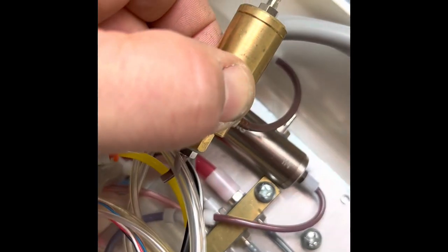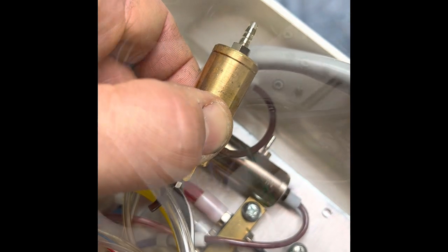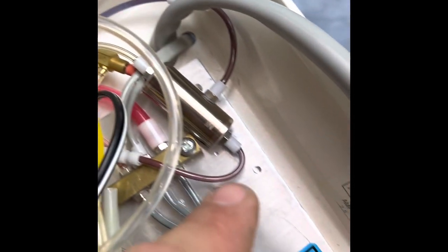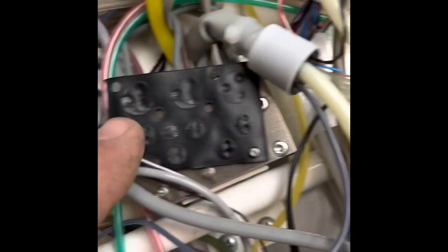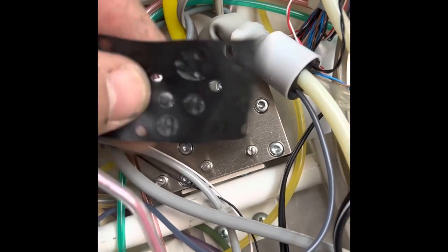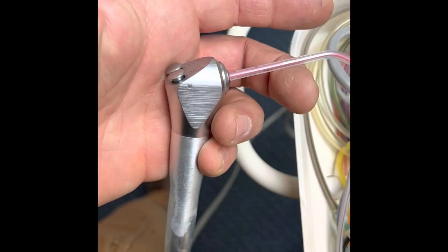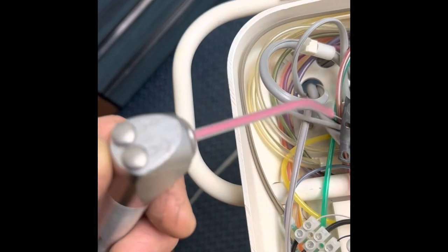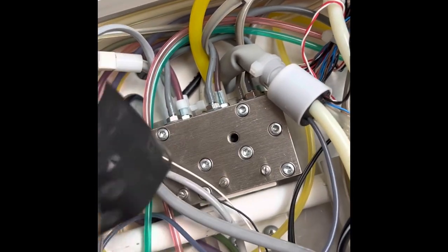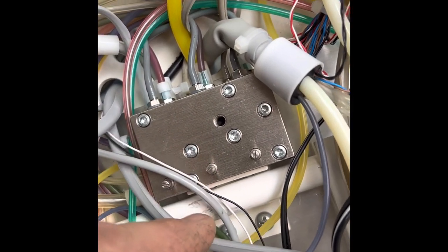Okay, it actually ended up being this diaphragm. The diaphragm was back-feeding air pressure through this line, and I only found it because I could hear it making that noise. This diaphragm was actually the reason this air-water syringe had air coming out on the water side. Very interesting problem. Yeah, crazy problems—always check the diaphragm.